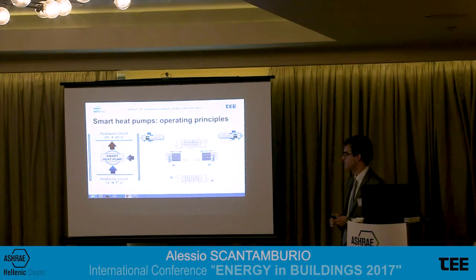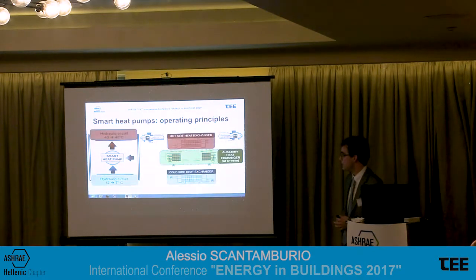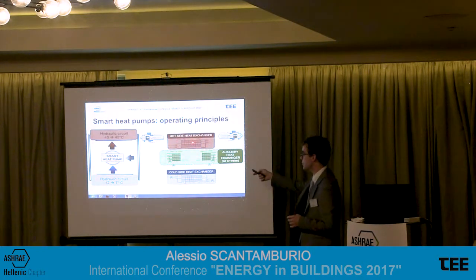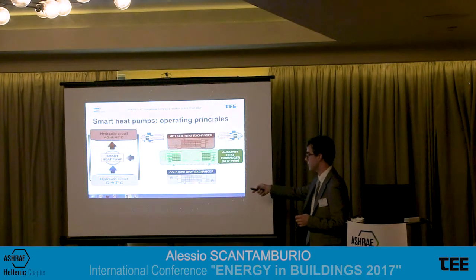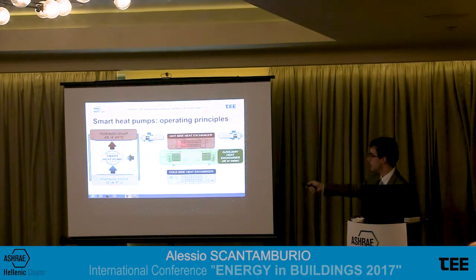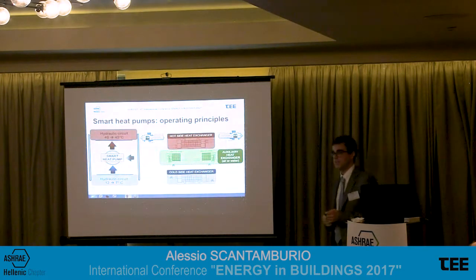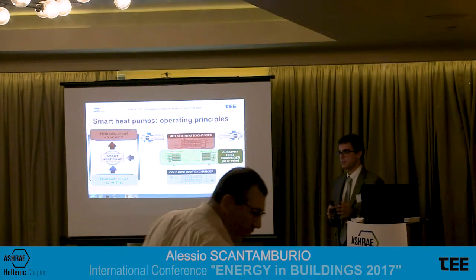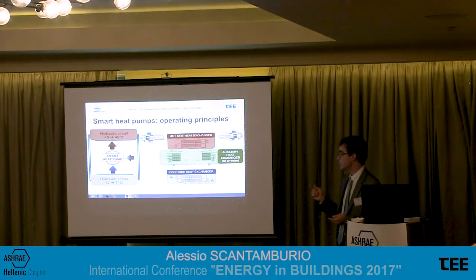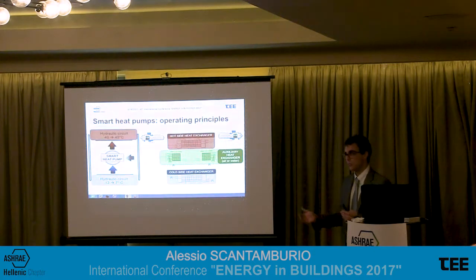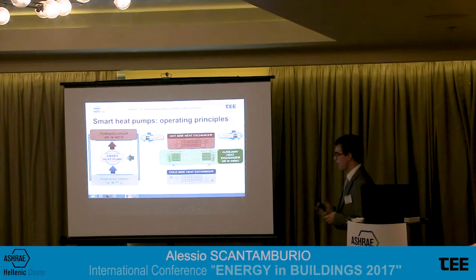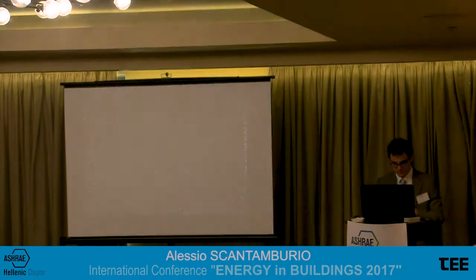Okay. This is a simplified view again of the refrigerant circuits of a four-pipe unit. We have three main sections. We have a hot side heat exchanger, which is always the condenser. We have a cold side heat exchanger, which is the evaporator, and these two are connected, of course, to the four-pipe of the plant, hot pipes and cold pipes. And then the key part of the four-pipe unit is this auxiliary heat exchanger. It can be an air coil or an additional water-to-water heat exchanger, depending on what type of unit it is. And it works either as a condenser or as an evaporator to exchange the remaining energy the building is requiring. Now we have prepared a short video to better understand the working principles, to have a better view, let's say.